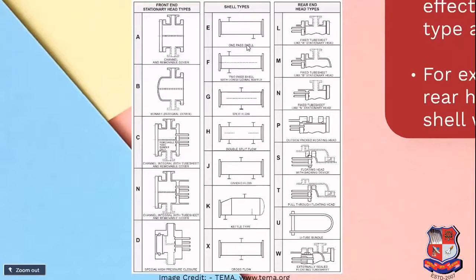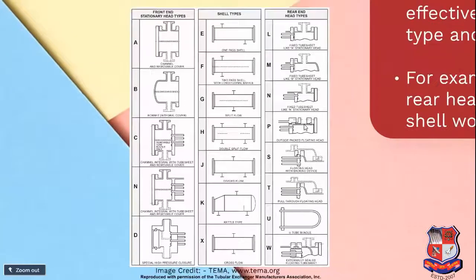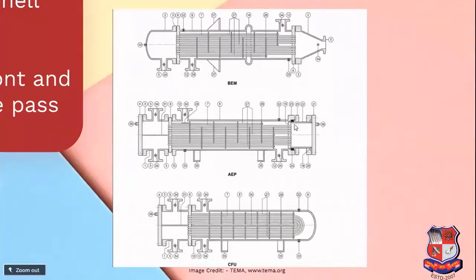Now next one was E. E stands for one shell side pass, and coming to P, which is a rear end head type, which is again an outside packed floating head. Now this is an example of a floating head type of heat exchanger. As I told you, it will help in expansion of a tube, but there is a packing which is done for prevention of leakage. It is outside the floating head, so it is said to be an outside packed floating head. Here you can see the 24, which is a ring which prevents the leakage of shell side fluid. So this is the packing which is done outside of the tube sheet.